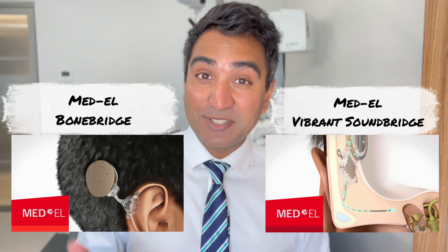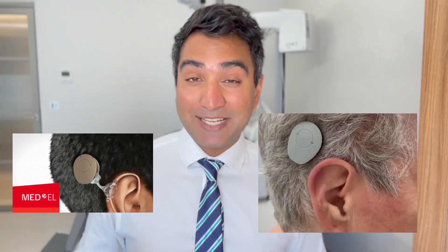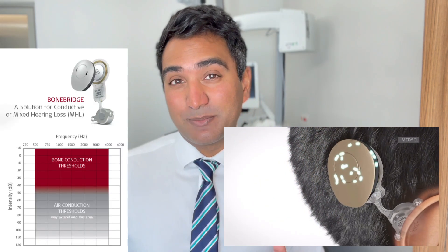In more recent times, MedEl tried to address some drawbacks of the BAHA with two devices: the MedEl Bone Bridge and the MedEl Vibrant Sound Bridge. The Bone Bridge works similarly to the BAHA, except the processor attaches via magnet through the skin, so when the processor is removed there is nothing physically visible from the outside. This avoids some of the skin and wound complications that have affected BAHA users. However, with skin as an obstacle, the device is slightly less powerful — your inner ear hearing needs to be 40 decibels or better to benefit on the same side, and 20 decibels or better for cross-hearing to the other ear.